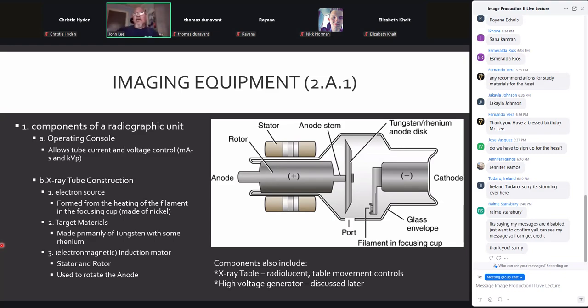So our electron source comes from the cathode. The heating of the filament: when we select our mA, we're going to select the amperage that's going to go through the filament, which causes it to heat up and boil off our electrons via the process of thermionic emission. Now, it's that movement of electrons from cathode to anode that is designated in milliamperage. Okay, the current going through the filament itself is amperage in amps, and then the stream of electrons is measured in milliamperage. Okay, that's important to remember, that distinction.